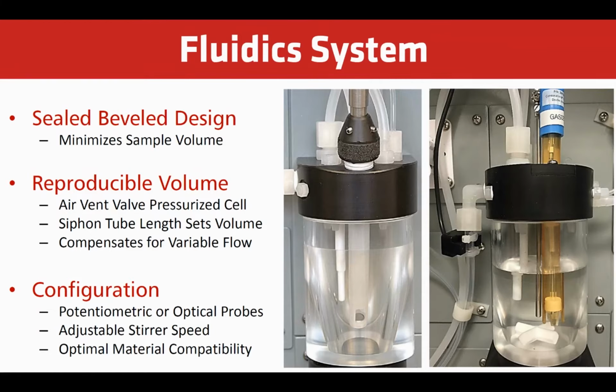The way that we grab the sample volume is we use what's called an air vent valve, and we allow sample pressure to build up slightly, and then we open this and it will drain out the siphon tube. At the bottom of the siphon tube, which you can see in both of these pictures, it's the white tube close to the probe, especially on the colorimeter one on the left-hand side, and just to the left-hand side of the metal rod or RTD that's in the probe-based one. So what happens is, as the sample drains out that siphon, it's always an exact amount of sample. So say if it calls for 10 mLs capture volume, every time it will be that. We do not rely on a pump or a valve or any other type of device to limit the amount of sample there, because it is all fixed on that siphon tube depth.